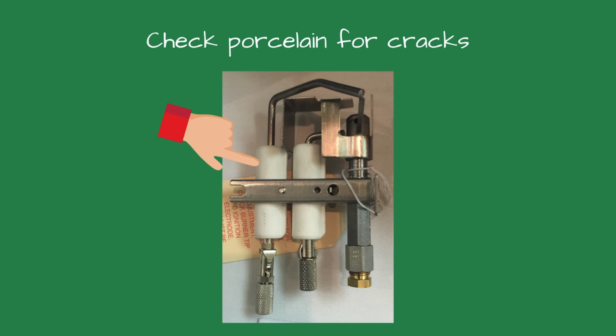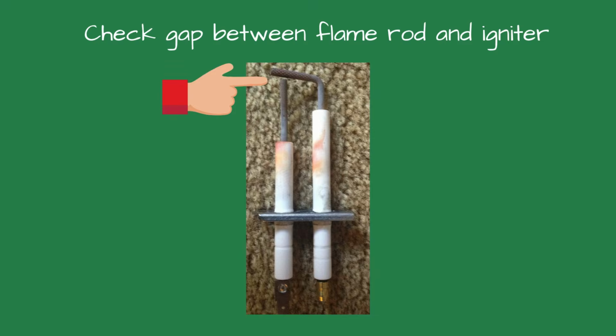Number 5, check pilot assembly condition. Look at the porcelain insulator. Look for cracks or tracks of carbon. Replace if damaged. Look at the electrode gap. Typically it's 1/8 inch, but check with the manufacturer. Too narrow of a gap and you get a weak spark. Too wide and you get no spark. Look for spark visibility. On many units you can see or hear the spark. Confirm it jumps to the pilot.